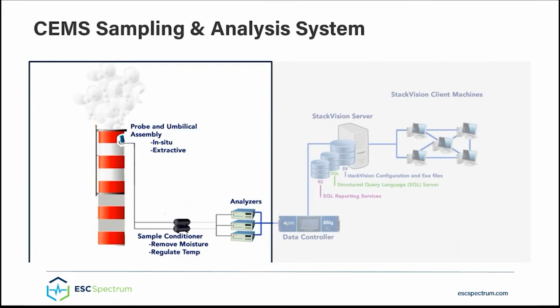travels down through an umbilical to a sample conditioner where moisture is removed. The dry air sample then enters the analyzers where the concentrations of contaminants are measured. For gas turbine electric power plants, that typically includes nitrous oxides and carbon dioxide. And depending on the analyzer, measurements can be read using analog or digital communications such as Modbus.